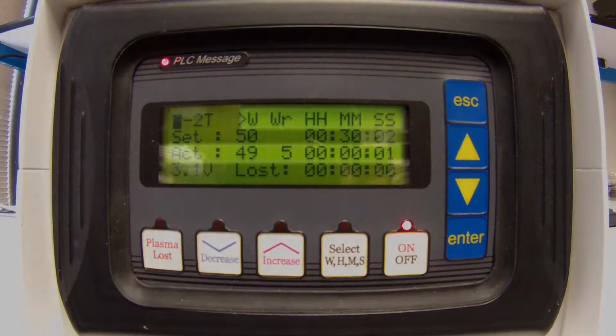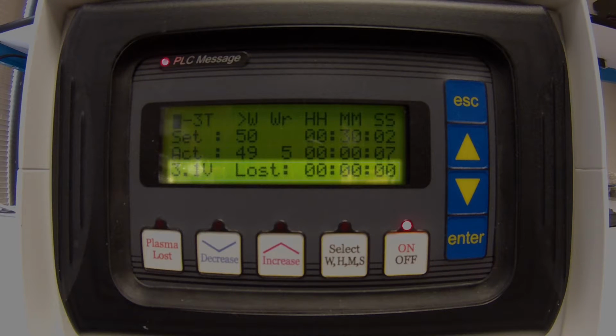Then if we look at the act line, that shows us the actual power that's being delivered, the reflected power, and the time elapsed. The last line shows the tuning voltage and the time the plasma was lost, if it dies while it's running.